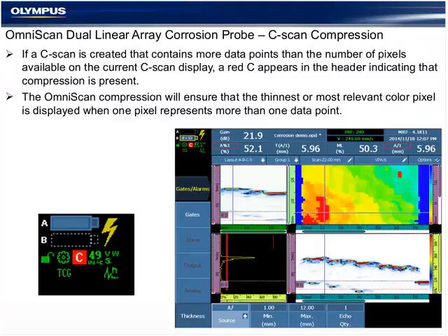Once we're on the A and the S scan, and again our views are available from the layout here, either in normal or full view, we'll see the side and end views of the data. As the C-scan changes size based on the size of the window, if a C-scan is created that contains more data points than the number of pixels available on the C-scan display, a red C appears in the header indicating that the C-scan is in a compression mode.